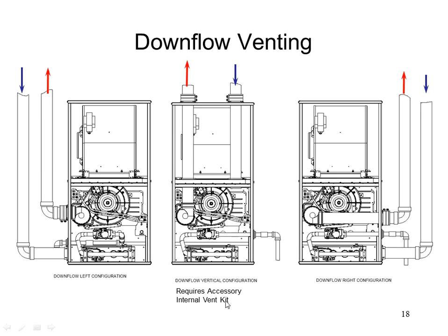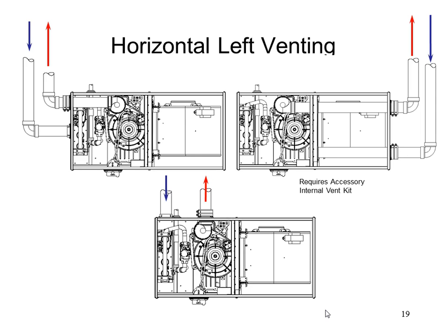However, if I do that, I need to get an extra venting kit accessory that basically cleans up these penetrations I'm going to make, to seal them up. And then I also have to keep in mind I'm now blocking access to my blower and my circuit board with these two pipes. So that would not be the preferred scenario, but if you had a really tight downflow application, you could do that. And the same thing happens with the horizontal scenarios.